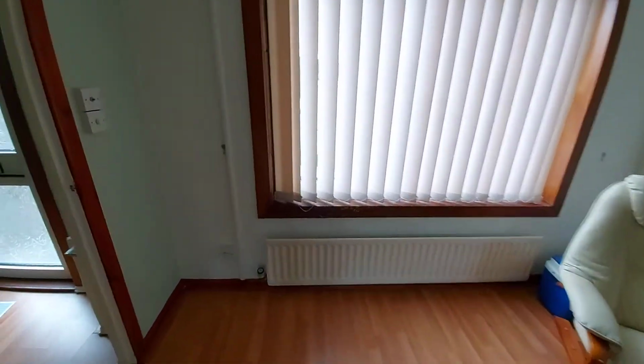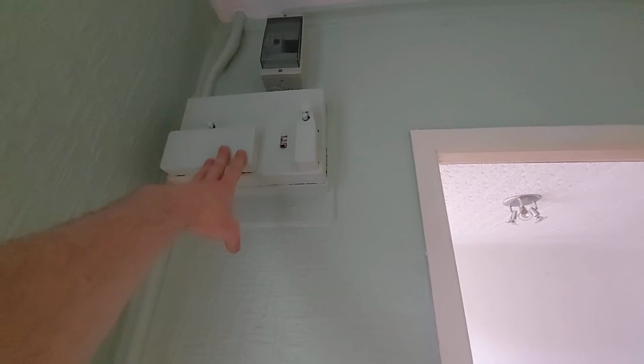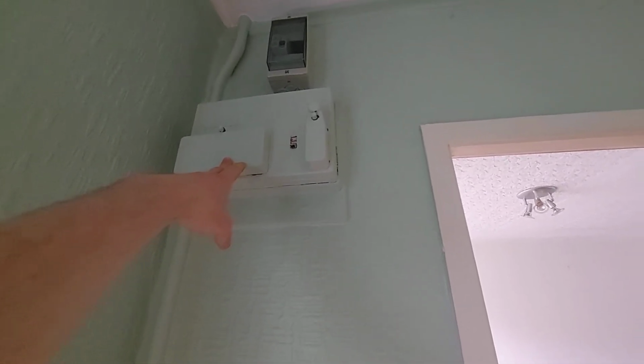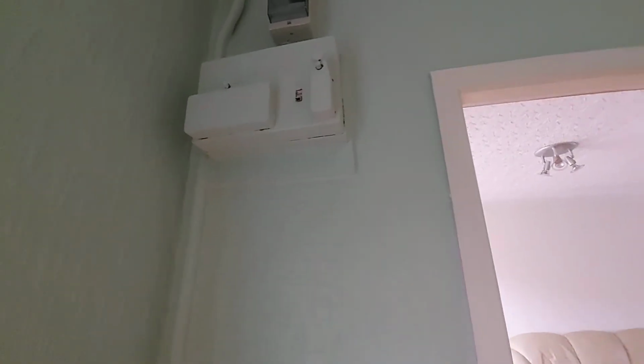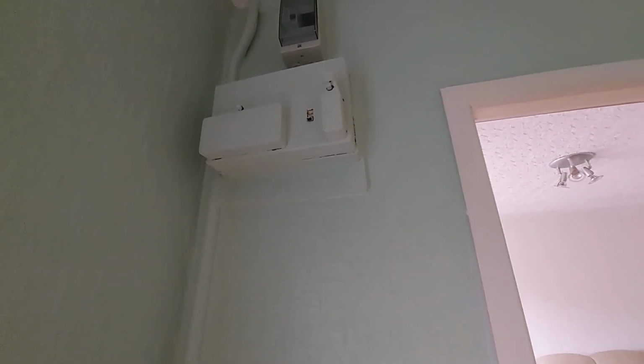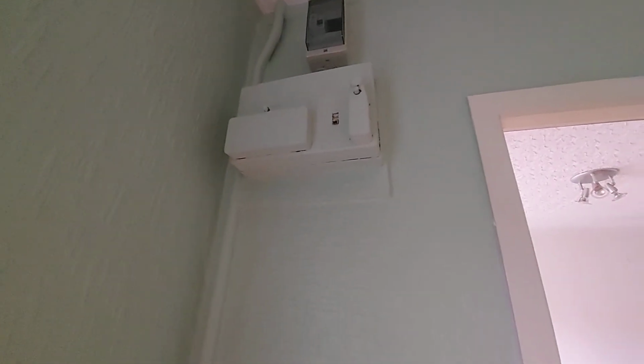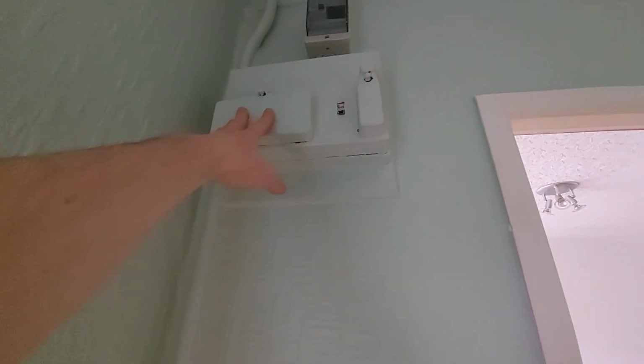So that's pretty much where we're up to. I've still got to install my charging point for the car, so I reckon I'll just rip out the connection for the electric shower - I don't like electric showers at all because they're very expensive to run - and run that cable down from there for now. Then I'll get this consumer unit replaced eventually, because there's no RCDs in it, so if there's an electrical fault where live touches the casing along with a fault with the earth, you'll just get electrocuted and die, because the fuse won't blow in that case. With an RCD, you'd be more protected.